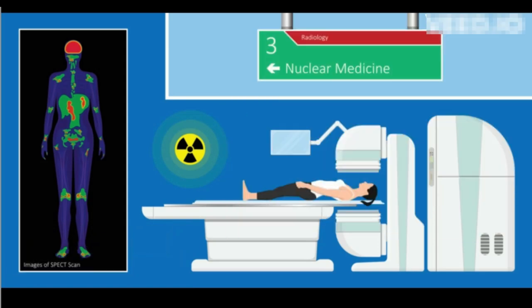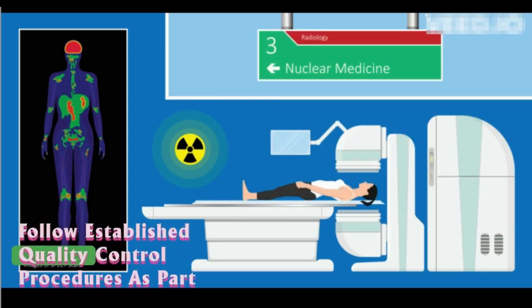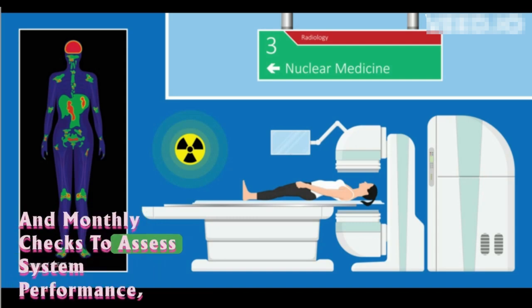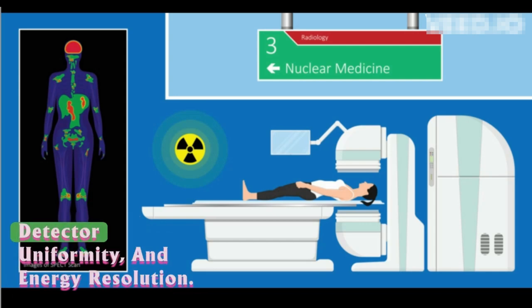Quality control procedures: Follow established quality control procedures as part of routine maintenance. This includes daily, weekly, and monthly checks to assess system performance, detector uniformity, and energy resolution.